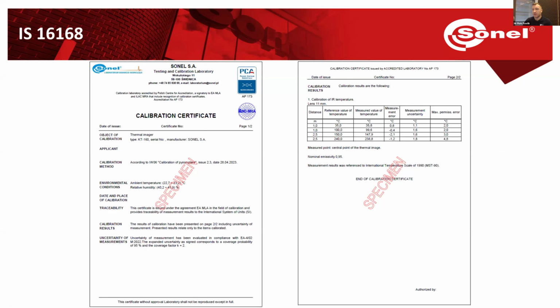All of the laboratories are accredited to the same standards, ISO 17025. Once you buy a new camera, you can also get a calibration certificate with accreditation from us, from Sonel. You can see here the type of camera, the serial number. This is just an example certificate, so there are no numbers, but normally there is a serial number, so this makes it traceable. We also see the conditions in which the camera was calibrated, as well as the results.